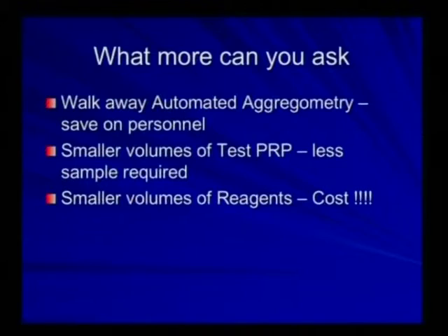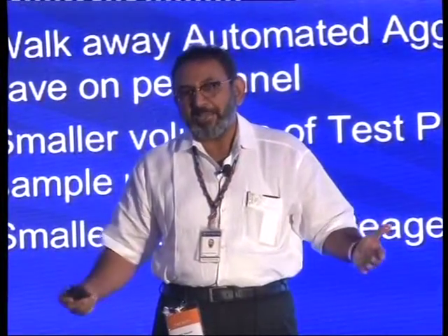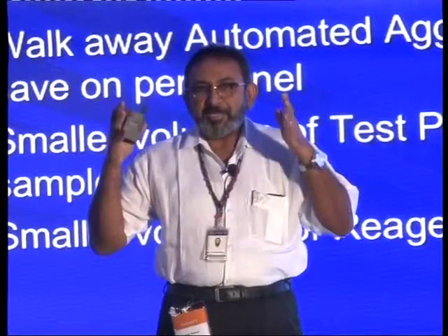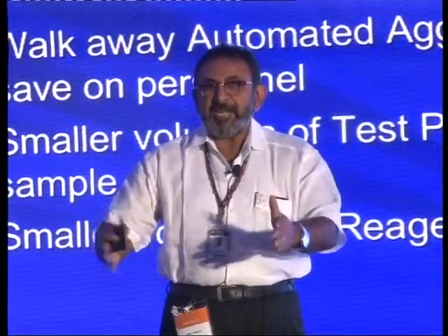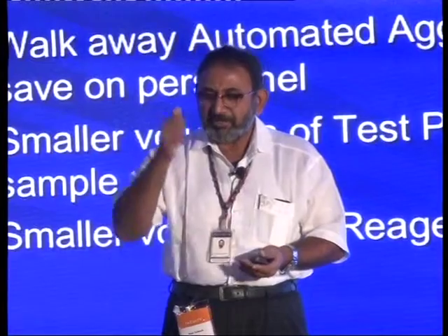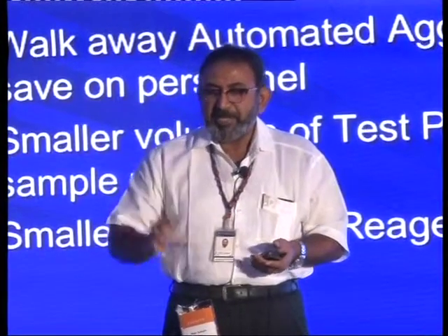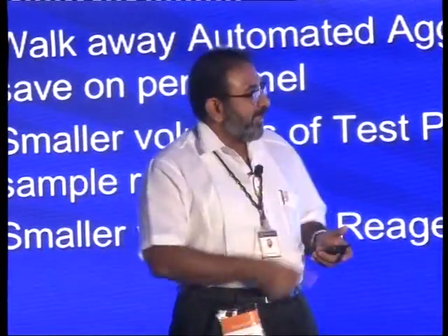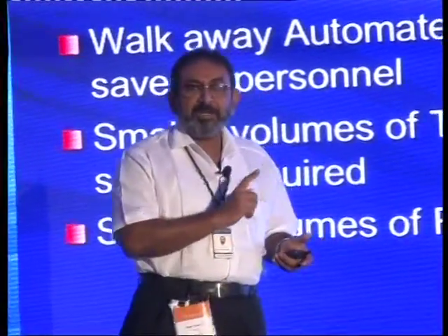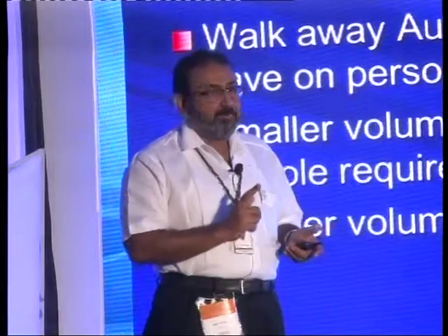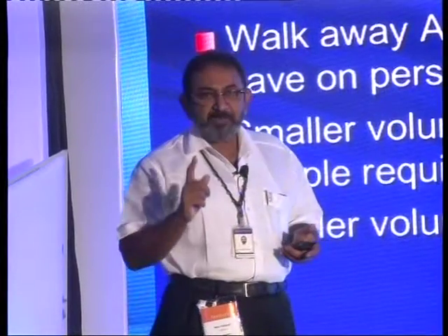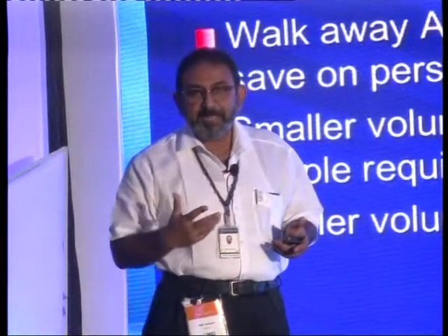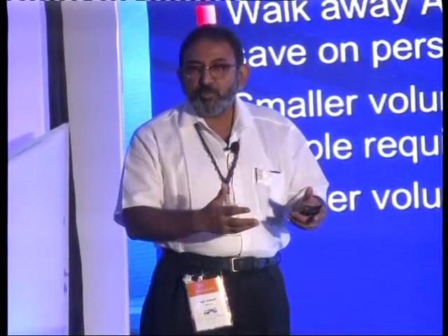If you ask my laboratory technologists what's the most painful test in the special coagulation lab, it is aggregometry, because one dedicated person has to go and stand. I do about 10 aggregometries every day, and add agonists to 1, 2, 3. It takes about 3 to 4 hours for them to finish the aggregometry for that day. Now I have a walk-away automated aggregometry.